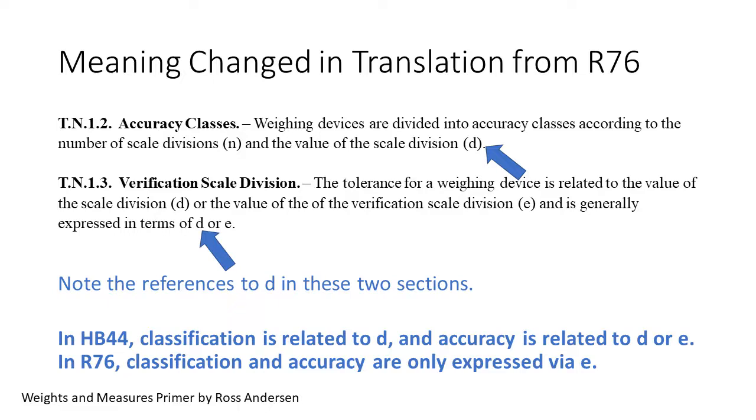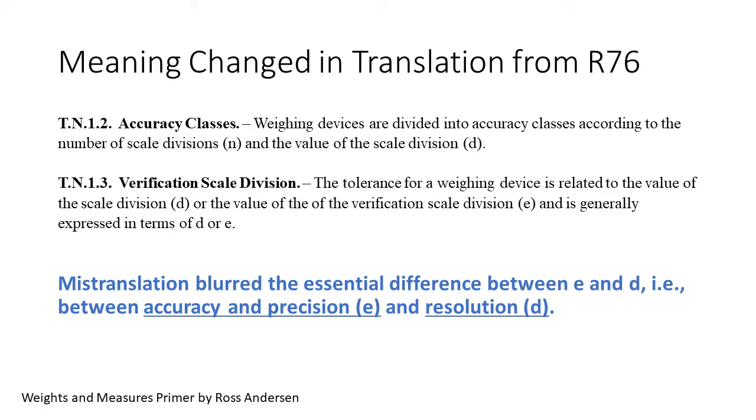Note the reference to D in both sections. Looking at the definitions, also adopted in 1984, we find that classification and tolerances are only tied to the verification scale division E, not to D. The definition D contains nothing about either topic. Classifications in Table 3 are expressed in D or E, even though TN1-2 only refers to D. The tolerances in Table 6 are exclusively in D, even though TN1-3 says D or E. Finally, when we compare to the parallel sections of R76, we find classification and accuracy are expressed solely in E. The mistranslations blurred an important distinction in R76 between E and D. It changed meaning significantly in several key sections of Handbook 44. The confusion that spawns from this change in meaning is far-reaching and very significant.